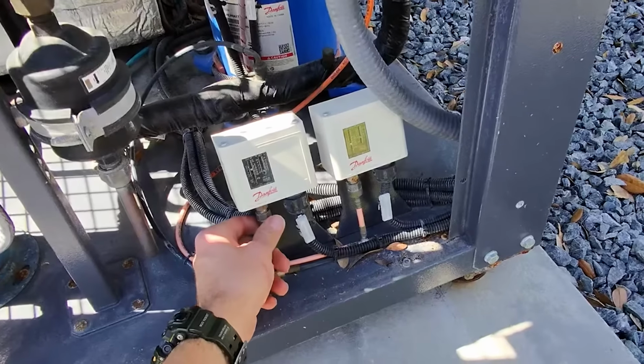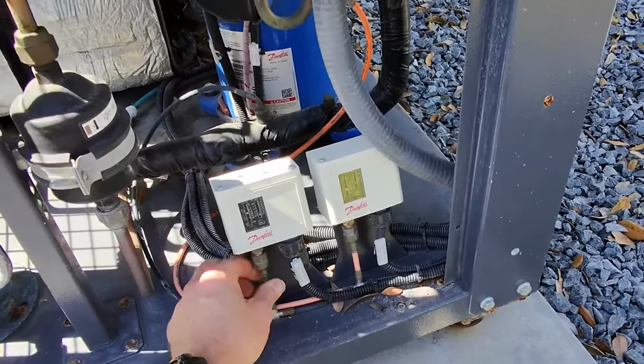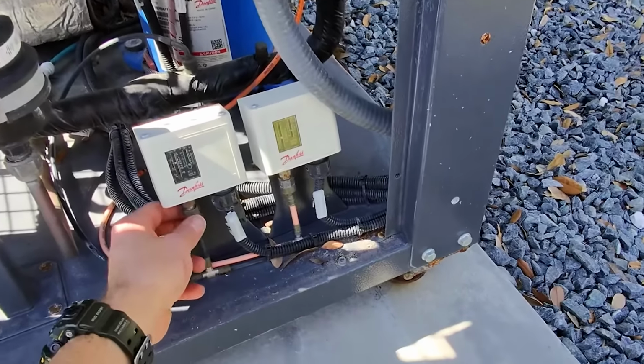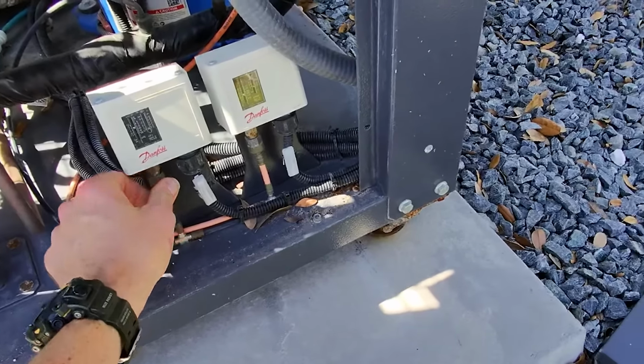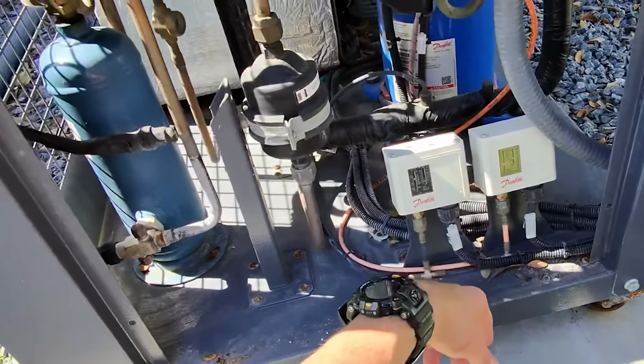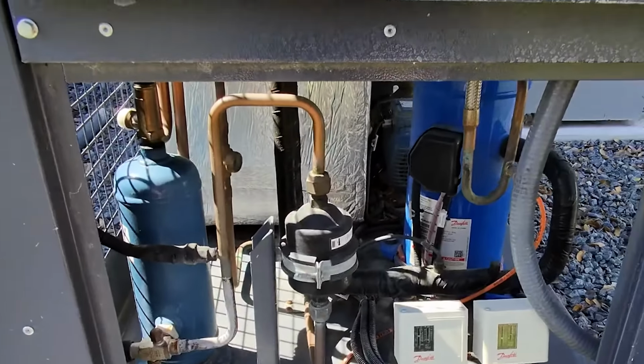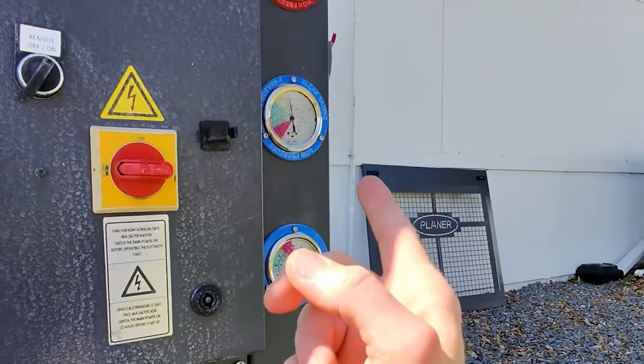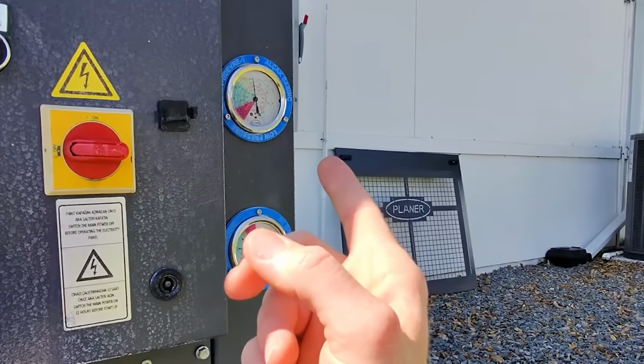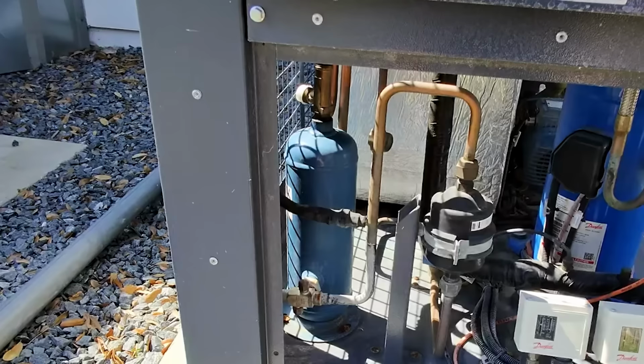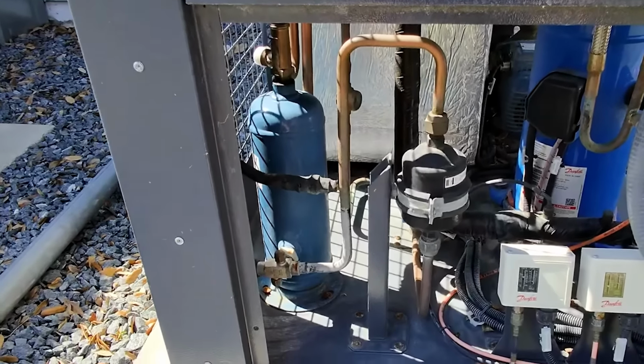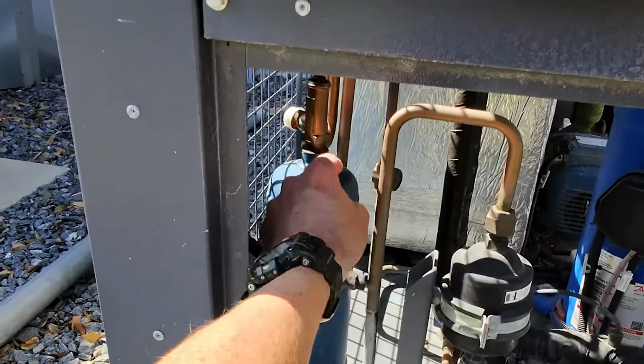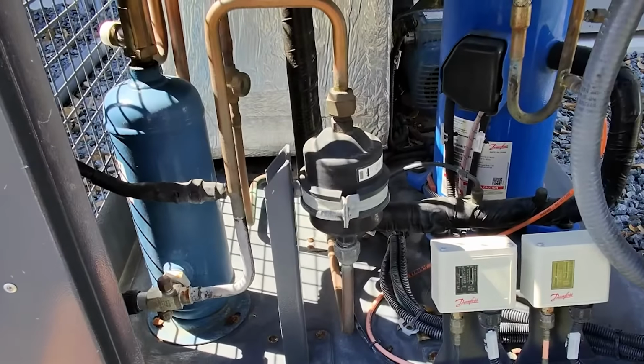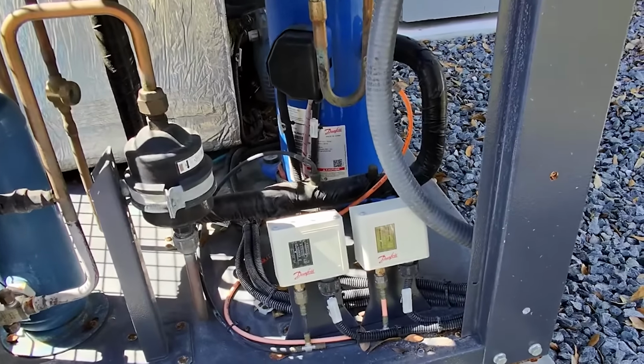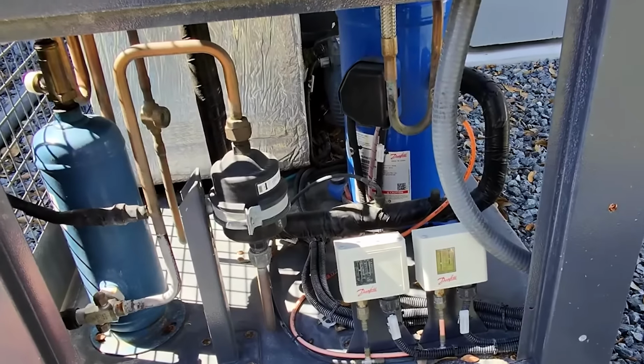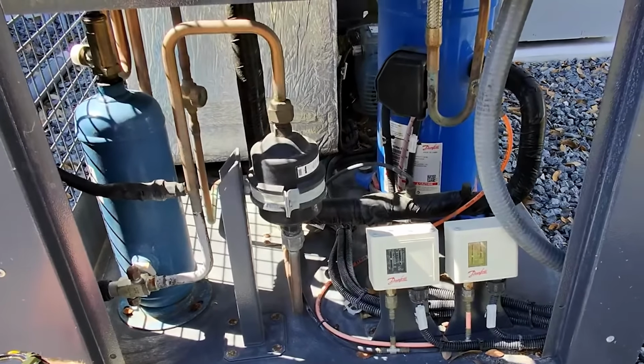They're using for pressure. Looks like this is low pressure. Cut in differential, cut out differential with Danfoss connections, both on discharge and suction. Then we've got pressure gauges on the system, but I am curious as to what we're looking at here. We do have some oil on top of this, but yeah, sight glass fills slightly with liquid before it cuts off. So let's get some gauges and gauge up and see what we can see on the pressure side as to maybe why this compressor is cutting off.